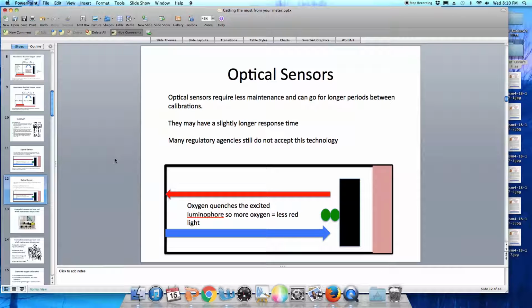There are a number of very good advantages to optical sensors. They require a lot less maintenance and can go for longer periods of time between their calibrations, although they may have a slightly longer response time. Most people I've spoken to said that they'll gladly trade the longer response time for much less maintenance. The dissolved oxygen optical sensors may require as much as 40 seconds per reading. Unfortunately, many regulatory agencies still do not completely accept this technology.